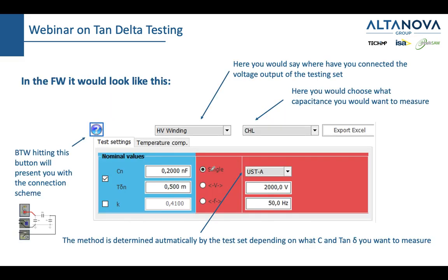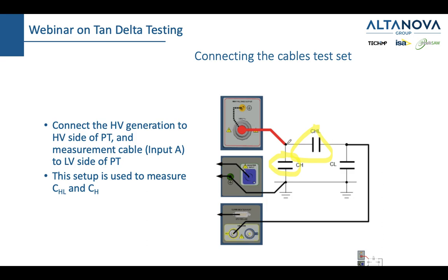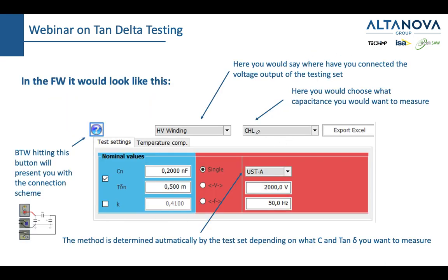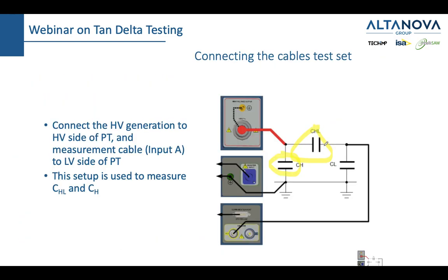And then what you need to do is go into the application, and this is now the good part. In our application, when you click this drop menu, you answer the question, where have I connected the high voltage generation coming from my test set? I can connect it to a high voltage winding or to a low voltage winding. Or if I have a transformer which also has a tertiary, it can also be connected to the tertiary. So right now, I have connected to the high voltage winding, and then I answer the question, what do I want to measure? CHL, which is this, or I can measure CH, or I can also measure CH plus CHL in one shot. So these are three things which I can measure with this setup.